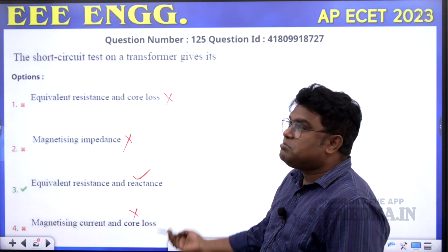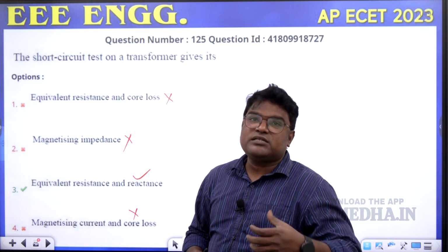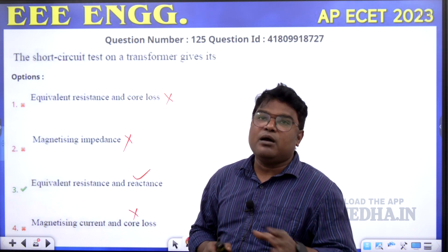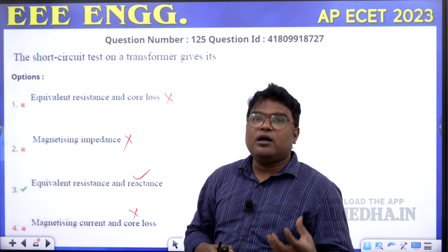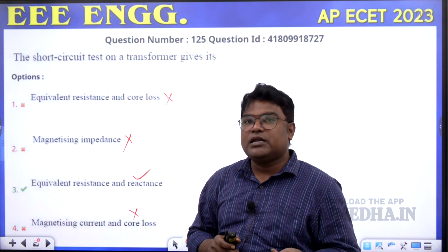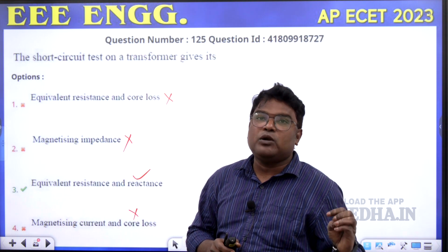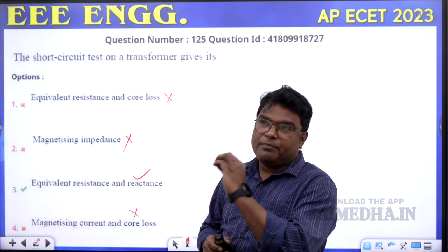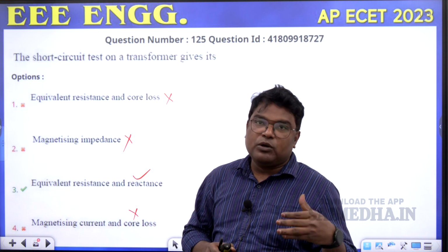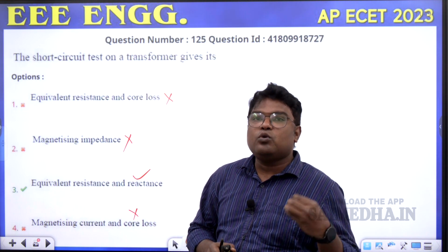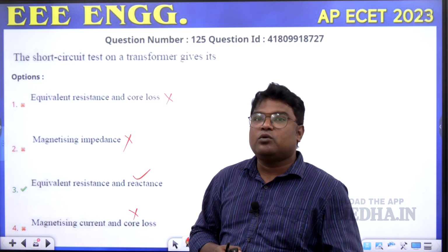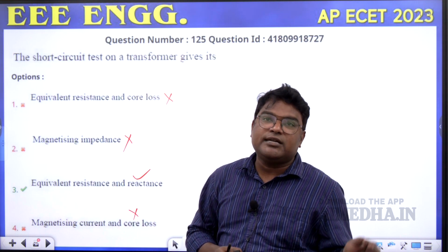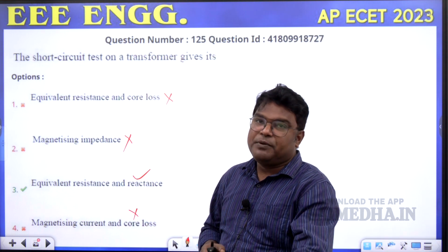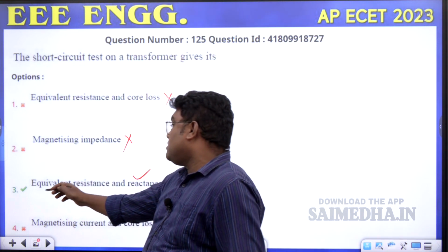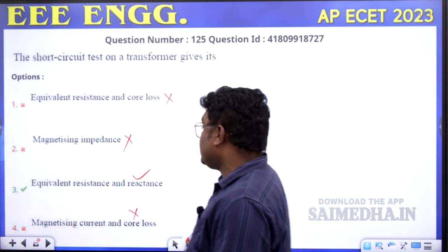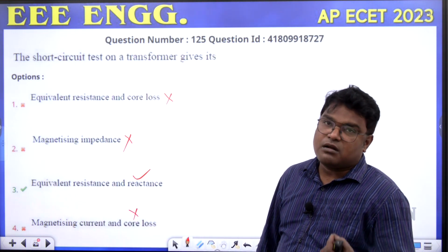So what are the objectives of the short circuit test? This test is conducted to find out the copper losses, to find out the series branch parameters of the equivalent circuit, such as the total resistance referred to the primary side and total reactance referred to the primary side, and also to find out the per unit steady short circuit current, percentage resistance, percentage reactance and percentage impedance of the transformer. So in this question, the option mentions the equivalent resistance and reactance of the transformer.